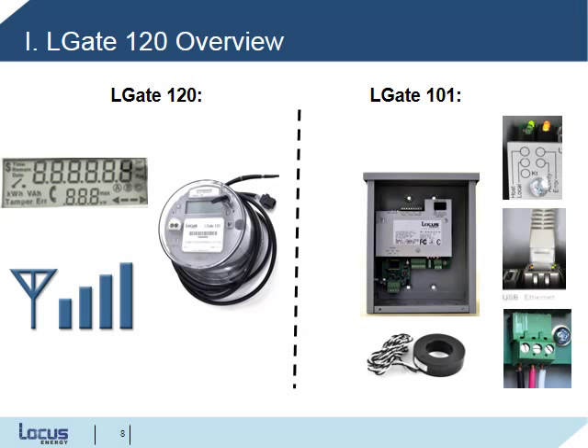So we've expanded the dataset with these new meters, but we've also simplified the installation. Here's how the LGate 120 differs from our previous model, the LGate 101E. Unlike with the LGate 101, the LGate 120 does not require an external CT to measure PV system output. This eliminates the possibility for one very common point of installation error. In addition, the LGate 120 does not require a separate voltage reference from a dedicated 2-pole breaker on the electrical service panel.